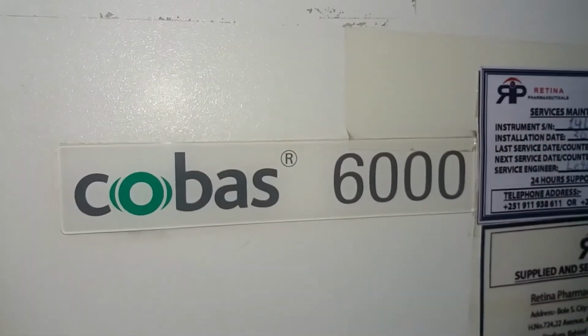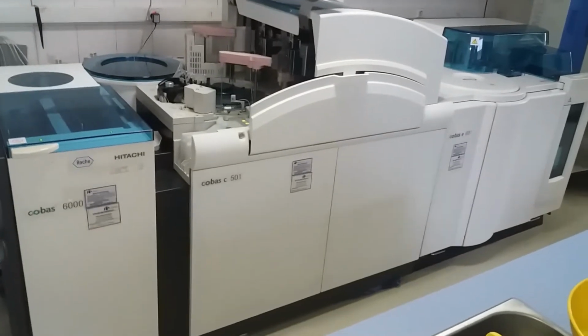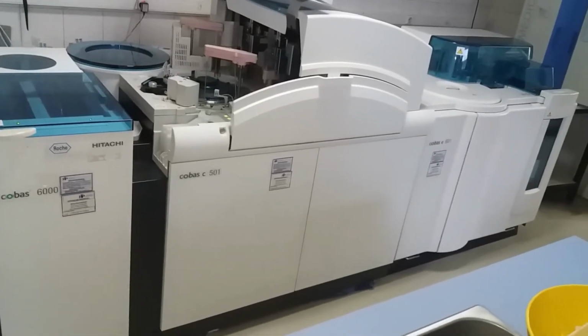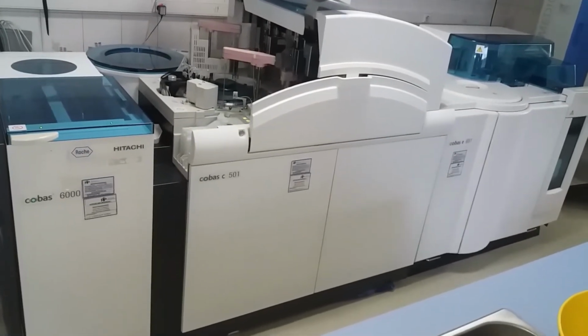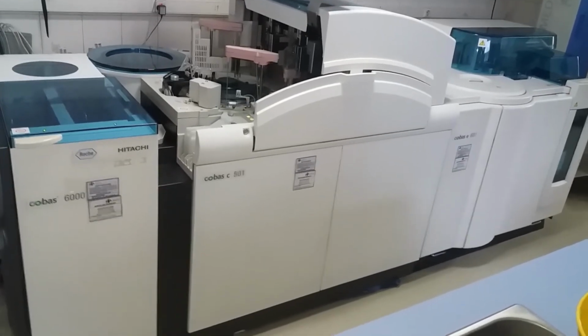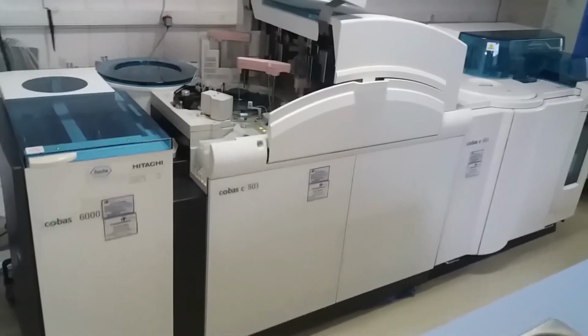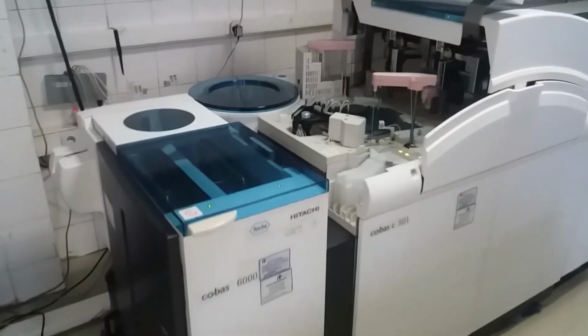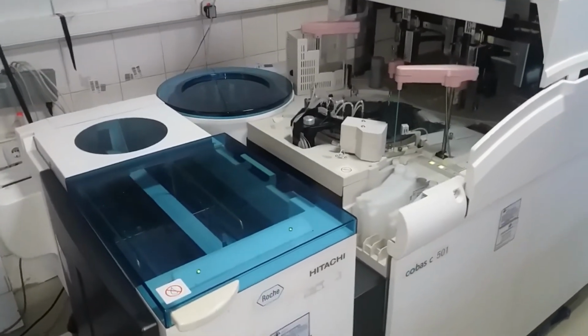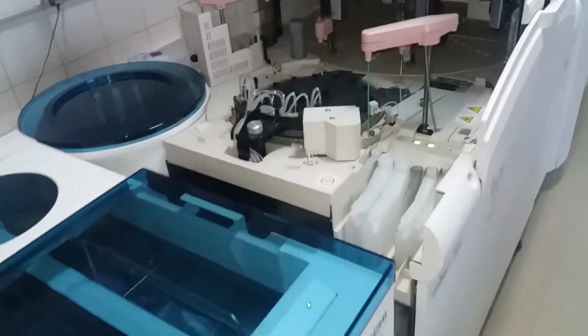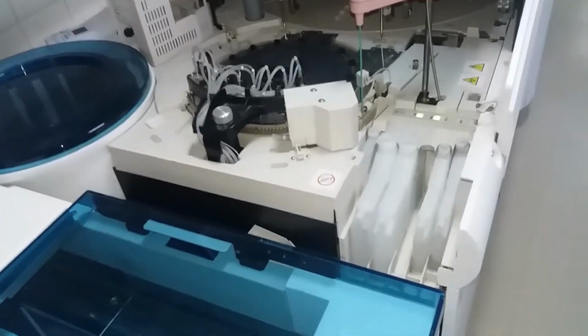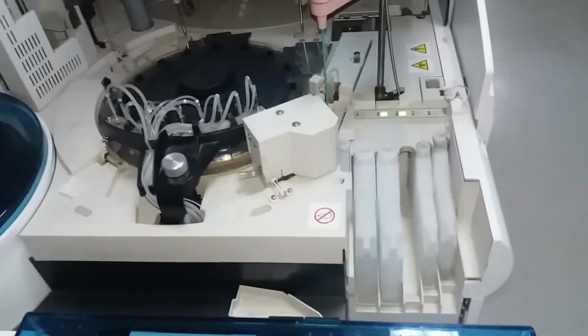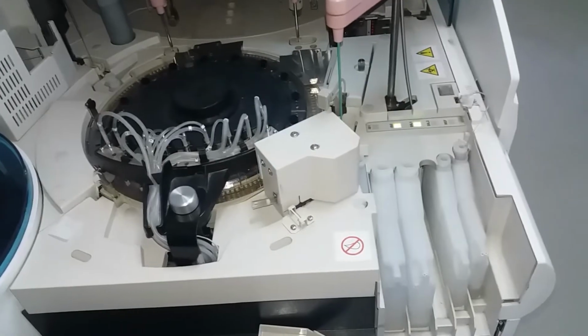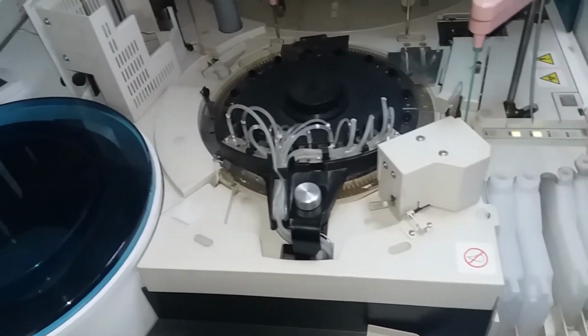Test methods employed on COBAS 6000 are of three types. These three test principles or methods of COBAS 6000 are: 1. Absorbance measurement photometry for most clinical chemistry tests. 2. Indirect potentiometric measurement, ion selective electrode. 3. Electrochemiluminescence for immunoassays.